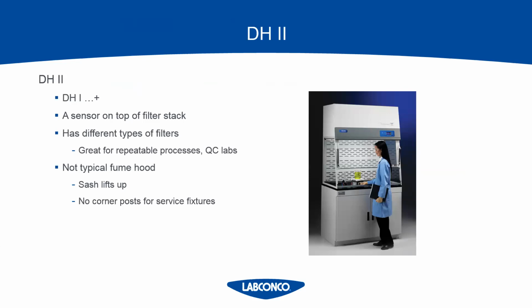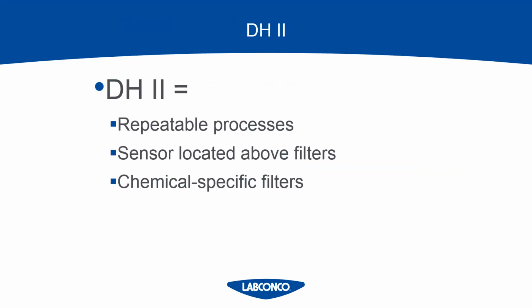When you use the exact same amount of chemical for the exact same duration all day, every week, you're going to know how long those filters are going to last. So you'll be prepared to replace those when the sensor goes off. If there's a limited use application that's repeatable and you don't need service fixtures or electrical outlets, then this is really the perfect hood for you. At Labconco, we call this the Paramount. The DH2 is the Paramount. So here's in a nutshell: they're great for repeatable processes, they have the sensor located above the filters, and they use chemical-specific filters.